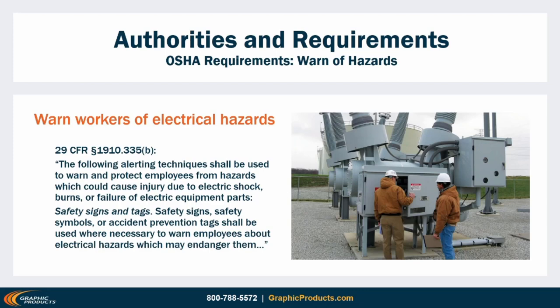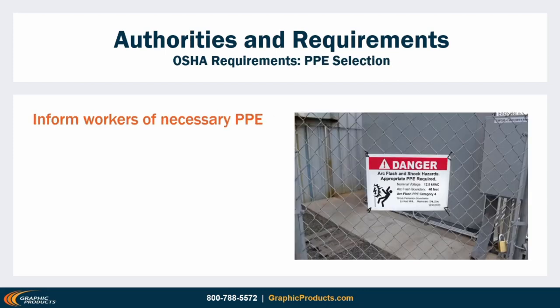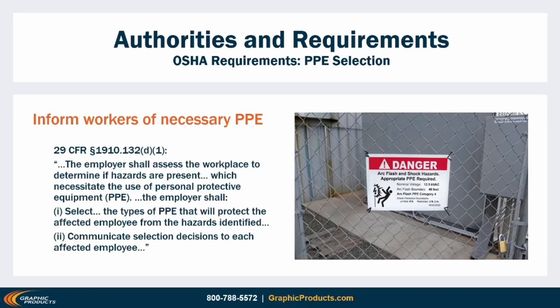OSHA gets more specific when it comes to hazards. The law mandates the use of safety signs to warn and protect employees from hazards which could cause injury due to electric shock, burns, or failure of electric equipment parts — this clearly includes arc flash hazards. Wherever a workplace hazard calls for PPE, employers must determine what PPE is needed, provide that equipment, and communicate the necessary information to employees. For the communication part of the rule, labels are a simple and effective solution.